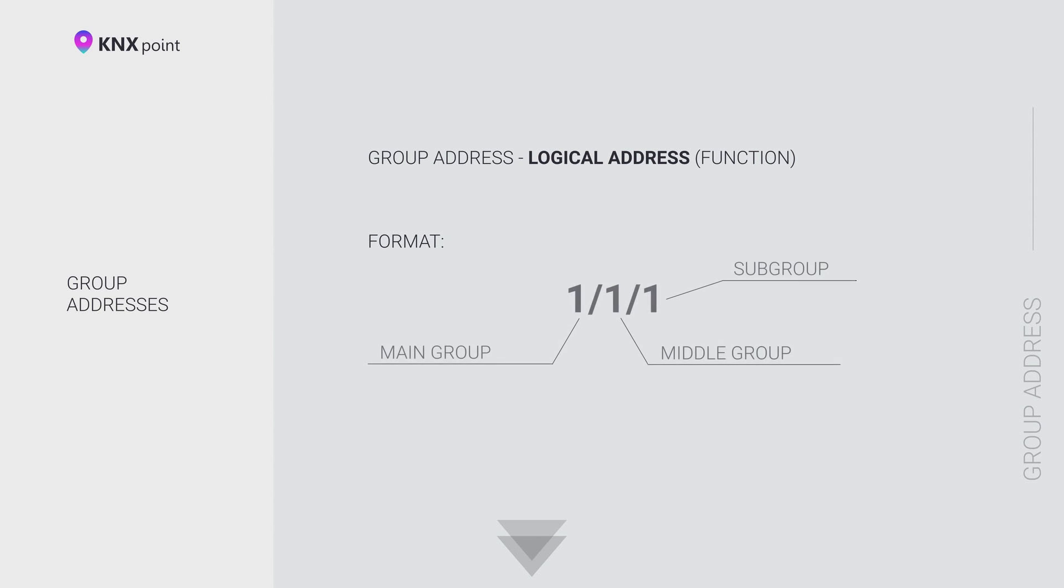The transmission of commands over the bus is carried out using telegrams, which are transmitted to their destination address. Destination addresses are called group addresses. Multicast addresses have a specific data type and provide the communication between devices. From a system setup point of view, a group address is a function in a KNX system.